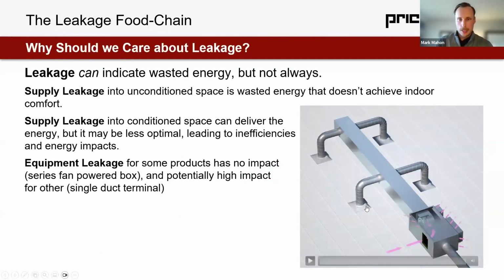So why should we actually care about leakage? I think that's an important component to the discussion as well. Leakage can obviously indicate wasted energy, but that's not necessarily always true. Supply leakage into an unconditioned space would be wasted energy that isn't achieving comfort or isn't achieving ventilation. It's a problem, and it's really just waste. However, supply leakage into conditioned space, say we have an open ceiling and low pressure ductwork, we still might be delivering some of the energy or some of the outdoor air, but it's going to be less optimal. So essentially, we're losing efficiency, which is going to impact energy as well. And then finally, equipment leakage, do we care or not?